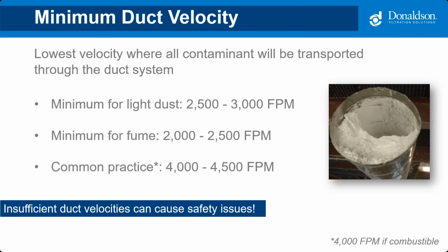For the light dust generated in battery manufacturing, the Industrial Ventilation Manual lists a minimum of 2,500 to 3,000 feet per minute, and a bit less for fume, 2,000 to 2,500. However, typically we suggest increasing that to 4,000 to 4,500, especially since 4,000 is the minimum if the dust is combustible. If the duct velocity is too high, it won't create any safety concerns, but it will require more energy to move the air through the duct. Ultimately, this could impact the size of the system fan as well as create issues such as increased noise, abrasion, and wear and tear.